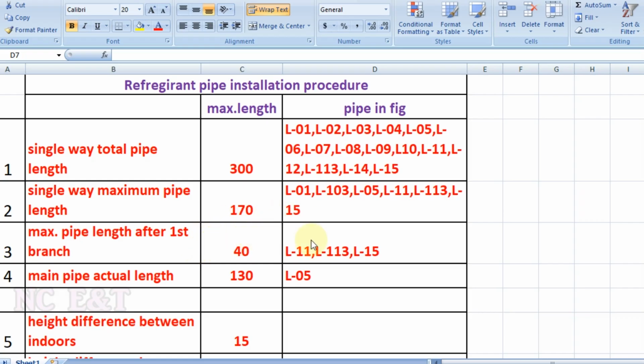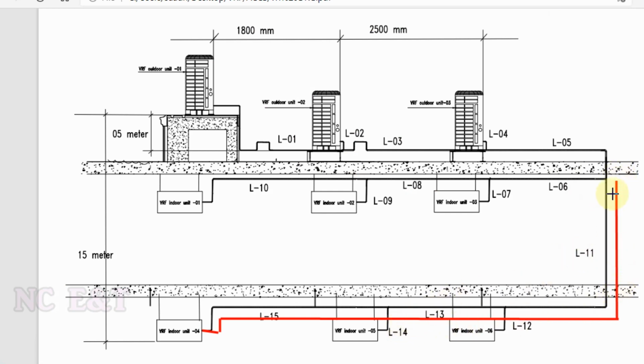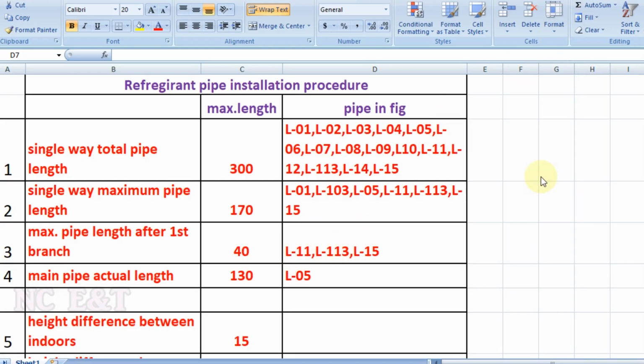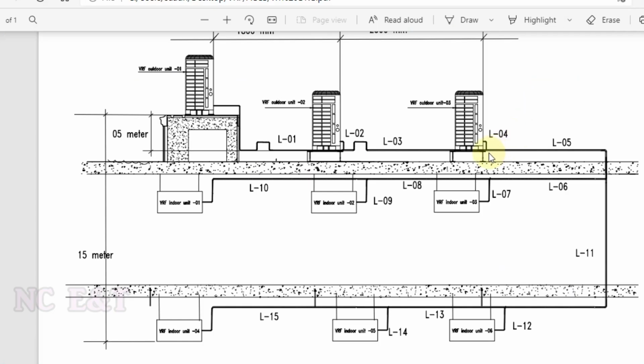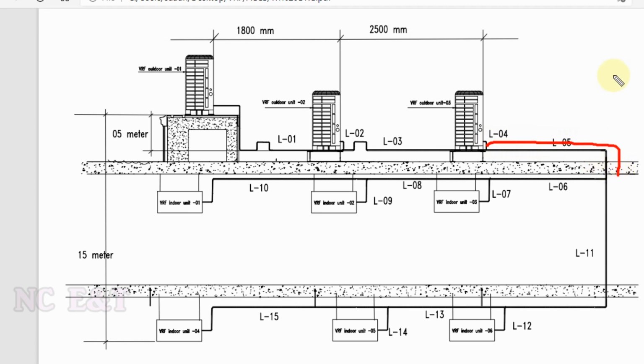Number 3 is the maximum pipe length after the first branch, which we have already discussed. This red marked line is the maximum pipe length after the first branch in our case, and it cannot be more than 40 meter. If we have any indoor unit after more than 40 meter, we need to design another circuit for those indoor units. Number 4 is the main pipe actual length. It cannot be more than 130 meter. It is the piping length between the last outdoor unit and the first branch. In our case it is L5, from the last outdoor unit up to the first branch, and we cannot have more than 130 meter. In our picture it shows very little, but practically it is the longest distance of the piping.